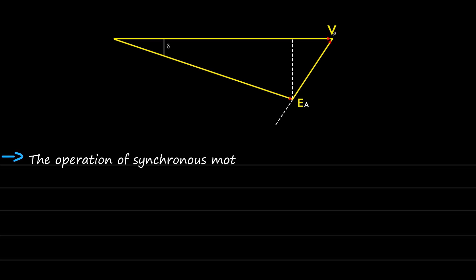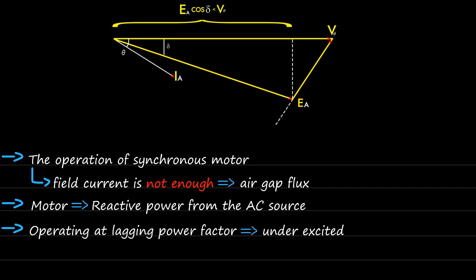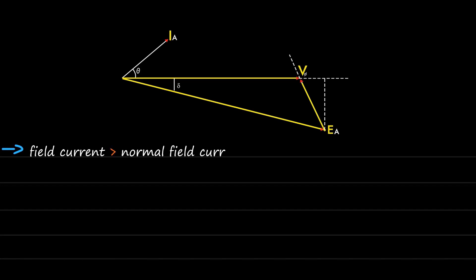From the discussion, we can summarize the operation of synchronous motor as: when the field current is not enough to produce the required air gap flux, the motor begins to draw reactive power from the AC source and is said to be operating at lagging power factor, and thus said to be underexcited.